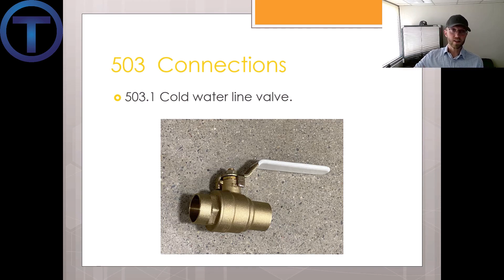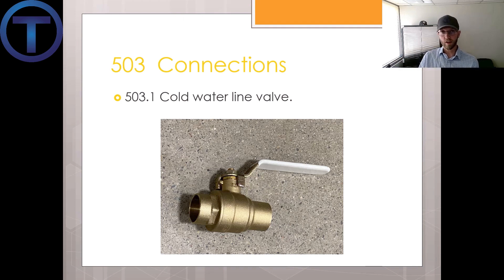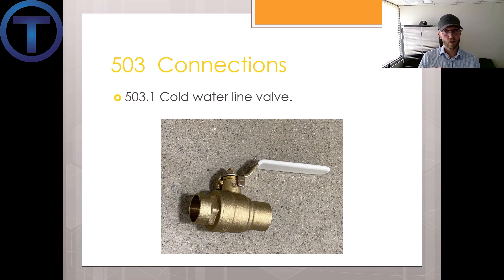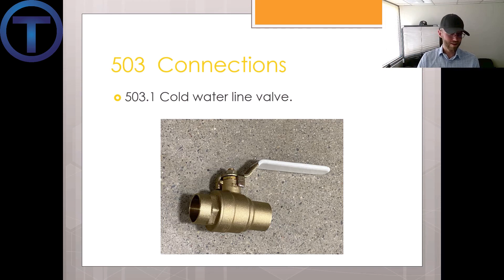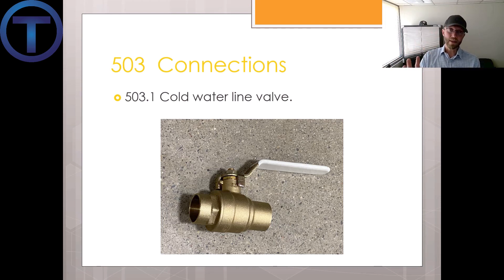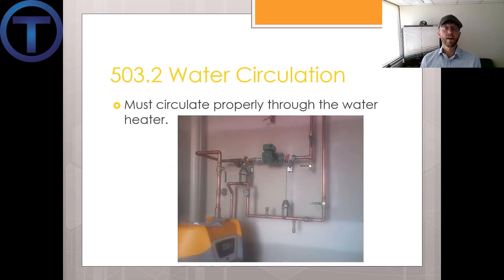It's not to serve other appliances — one valve cannot shut off two water heaters or anything else. Each one has to have its own shut-off valve on the cold side. Let's make this serviceable. This valve has to be accessible and on the same floor level.